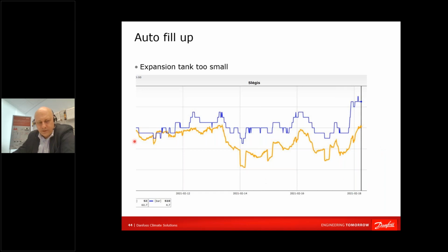Why is it too little? Because as supply temperature is rising, pressure is building up in the system. As temperature is decreasing, pressure in the system is decreasing. So the expansion tank is not working. Somebody has to fix it.